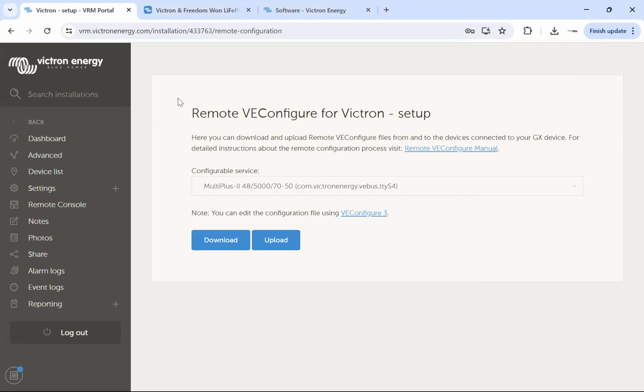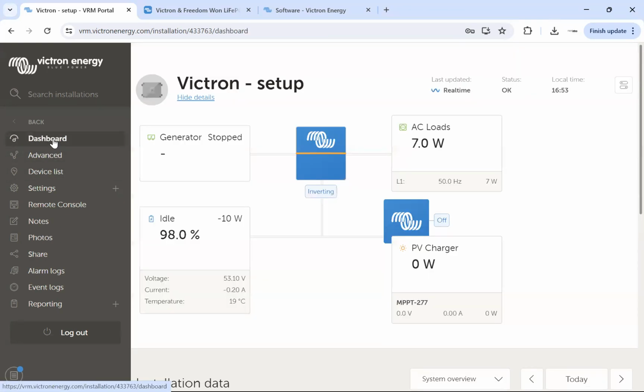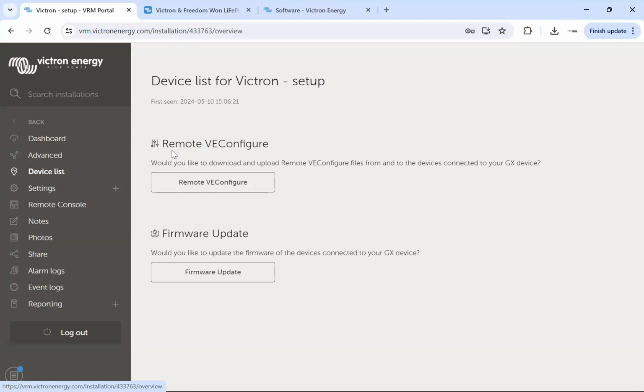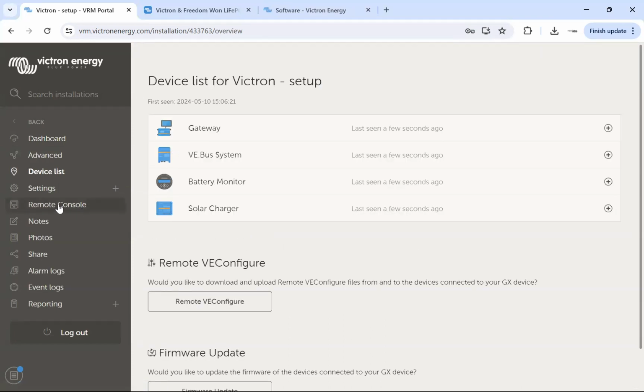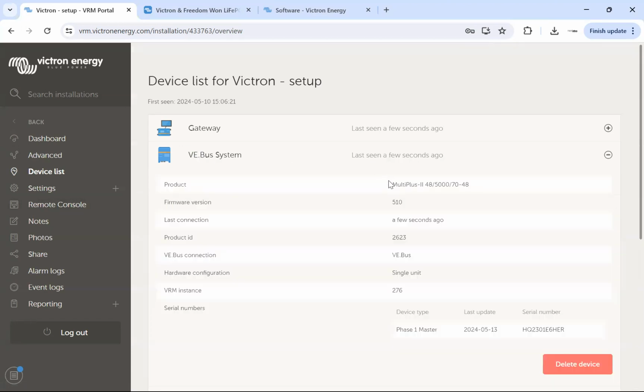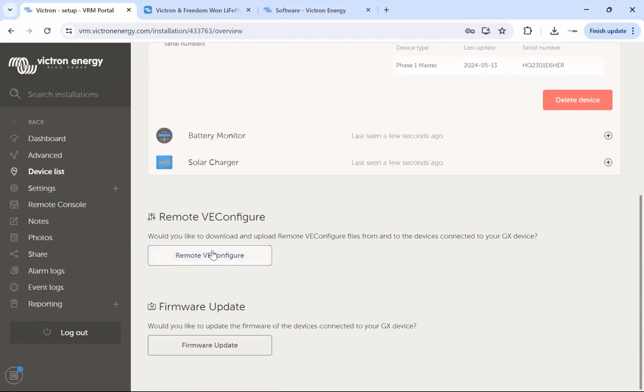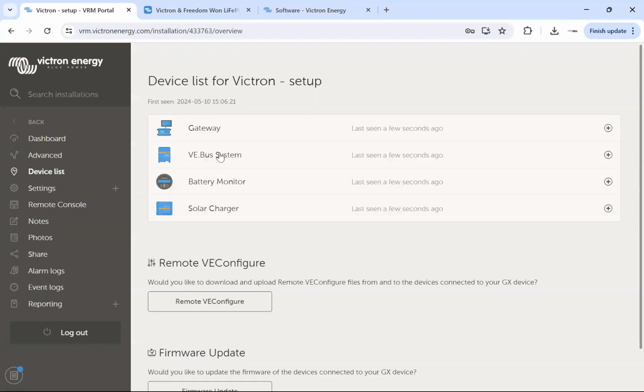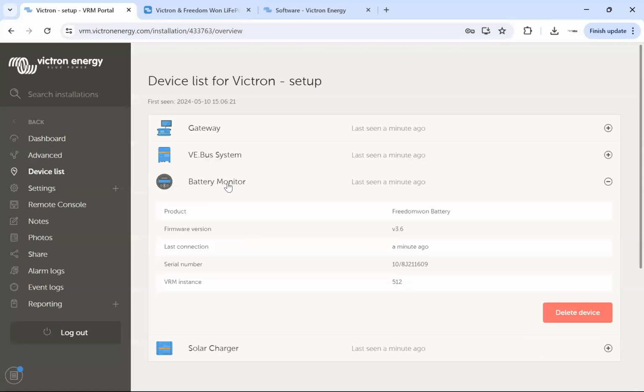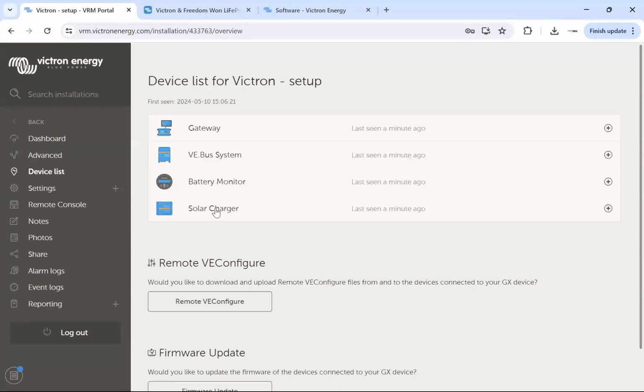So the last thing we need to do, one thing we haven't programmed, right? If we look at the device list, we have programmed the gateway, which is the GX device, and we did that through the remote console. We've programmed the VE bus system, which is the inverter, and we did that through remote VE configure. And we've got a battery on there. Now the battery's already programmed, we don't need to program that. The last thing we need to program is the solar charger.